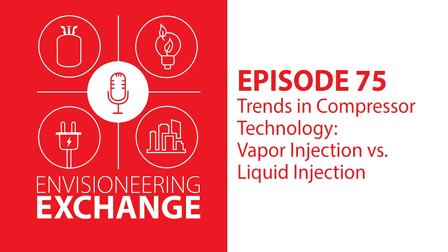And we talk about maybe the data center space, where they don't really care so much about cold climates, but they need those high saturated suction temperatures. Then maybe we're able to move the operation a little bit to the right-hand side of the compressor map, since we can now vapor injection or liquid injection to cool the compressor down. So I think there's some flexibility to play in some of those spaces as well, for sure.